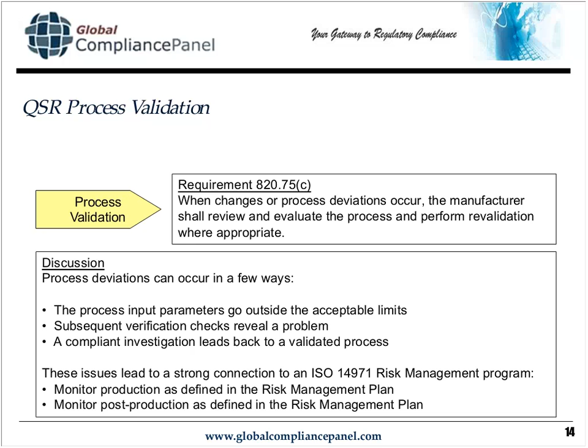The preamble tells us this is the requirement for process validation, and I do not have to revalidate processes just because they show up on a calendar. In other words, I don't have to have a master revalidation schedule. I revalidate processes when I have a change to the process or a process deviation occurs.